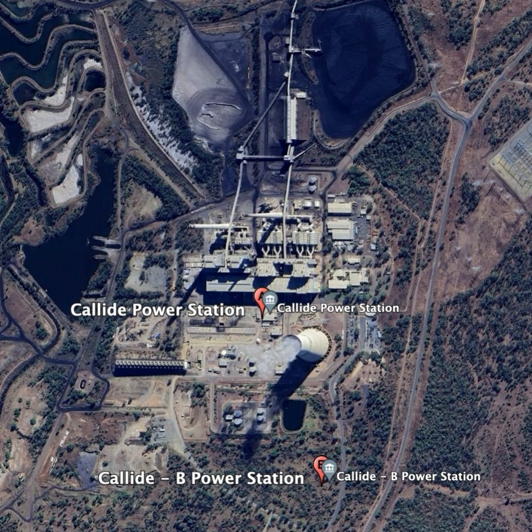At 1:32 p.m., the Unit C4 DC battery charger was reconnected to the main DC bus. At 1:33 p.m., the command to open the interconnector was given, and the Unit C4 DC main bus and DC distribution board buses rapidly dropped to nearly 0 volts. They went dead, or rather the voltage decayed from about 240 volt DC to 10 volts DC in only 3 seconds, since inductance and capacitance in cabling and equipment stops an instantaneous voltage change.